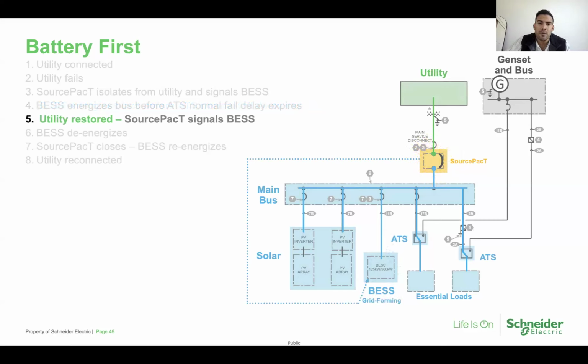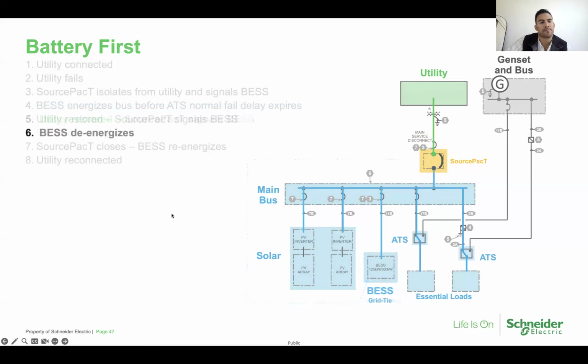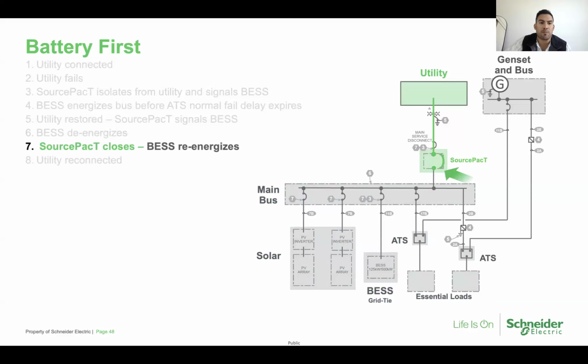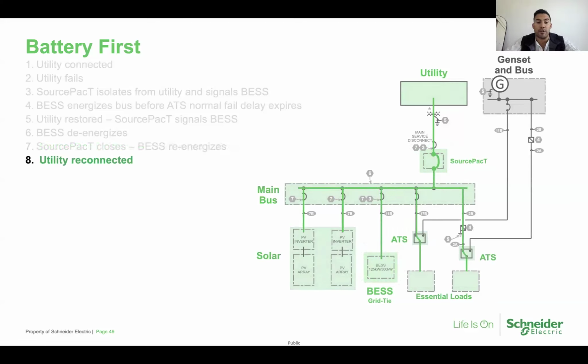Now, when utility is restored, we'll send the shutdown signal to the battery energy storage system. Again, SourcePacT has that controller that sends the shutdown signal when the utility is restored. Once the energy storage system is shut down and de-energized, SourcePacT will then close its breaker. Upon closing, the main switchboard will re-energize the main bus in your system, where the ATSs will again sense that power has been restored to source 1. You can also program the ATS controller so that as soon as they lose power, they have the same time delay as the SourcePacT device, where you can delay transfer to source 2 up to 6 seconds. And the same deal here for SourcePacT. Once utility is restored, that main bus is energized, and you're again operating in grid tied mode.